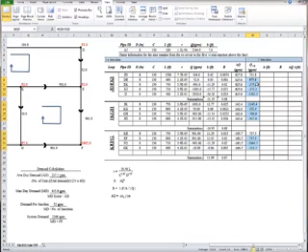Alright, the places where we do something different are where we have a shared pipe. For example, KE is a shared pipe. So I'm going to go here, KE, EK, whichever. You add on the delta Q from that loop, but then I have to go up here and subtract off the delta Q from the shared loop.